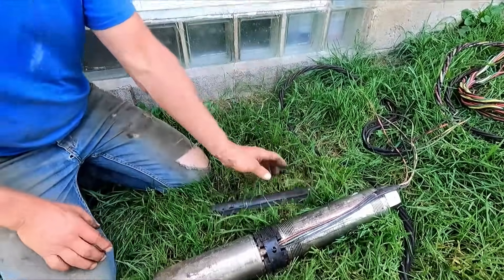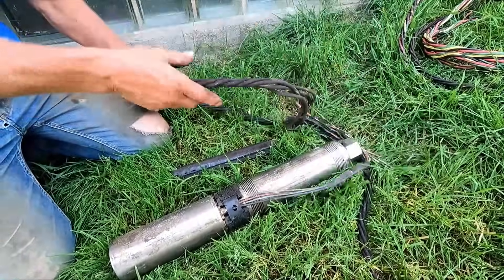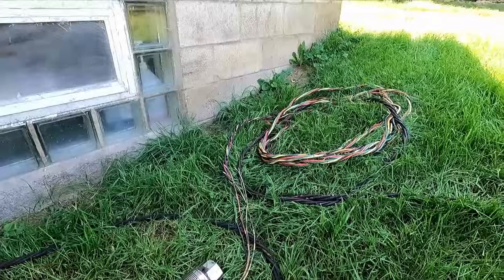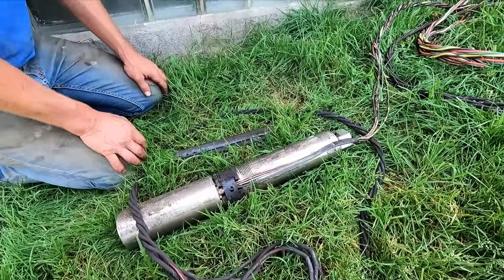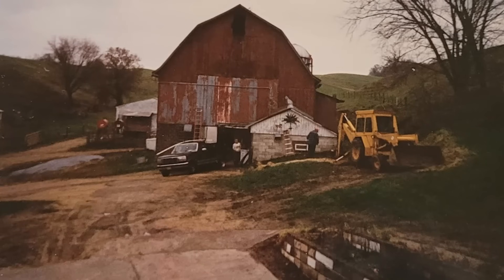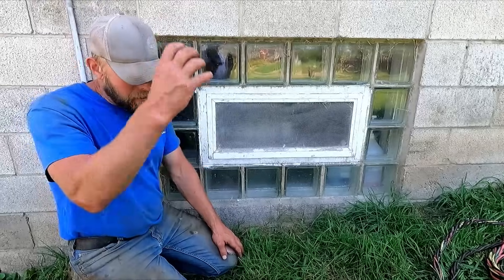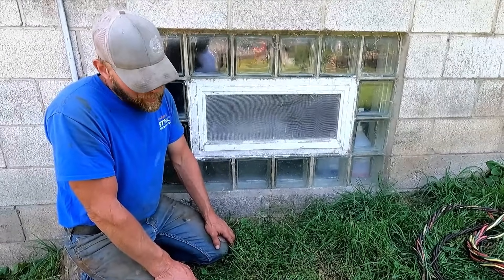They found out it was rubbing but it didn't rub the wire through, so the motor was bad. They shoved a new one down in there, then they had to flush the system. Being that the wiring had been down there for over 20 years, it was only smart to replace that wire too — it's pretty inexpensive, probably the labor is the more expensive part. This pump was down there since '95, so do the math. When we first drilled the well, within a month or so we had some sand issues, so they put a boot on — a long tube like a big filter — then eventually we pulled it up and took that off. The water was good after that.